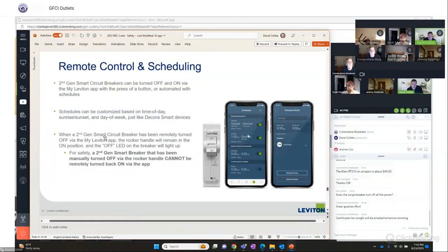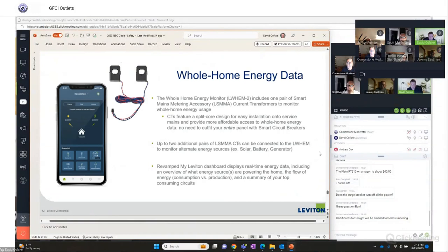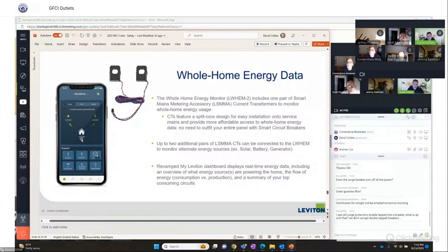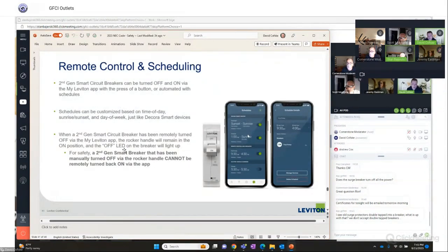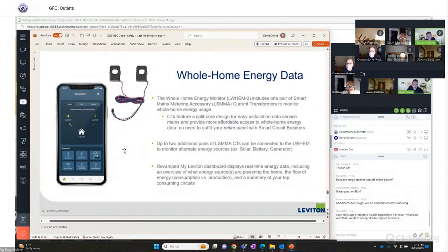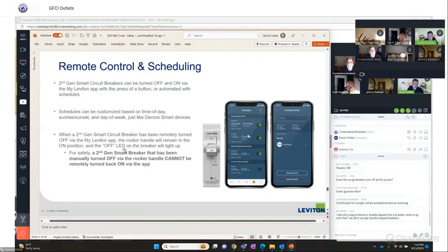this slide gets in and talks about the scheduling of the internal breaker. Here's where I was going to. With those CTs on there, based on that app, you can basically see what's being created by solar off to the left and what's coming off the grid on the right to power my home, which I think is 4,000 watts. So right from your phone, you're able to drill in and know where your power is coming from. If you want to see circuits individually, with these smart breakers, I can actually go in and look at what that circuit is drawing on that breaker. So I can get an overall 1,000 foot up view of what's going on in my house, but then I can really drill down to circuits and see what's going on in my house.